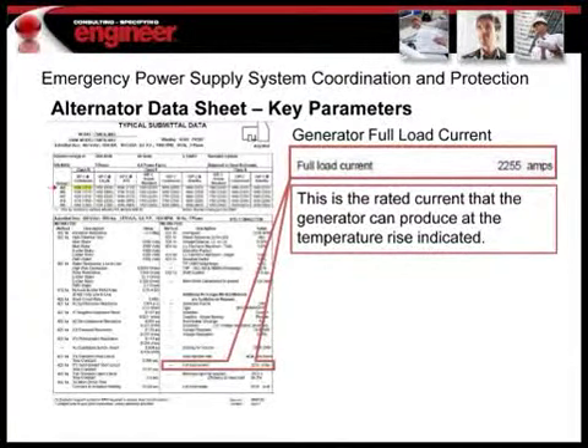The full load current of the generator is the next big item. Now, obviously, here we're looking at a 1,500 kW generator. So this is the rated current that the unit can produce, and it's always tied to the temperature rise that we're talking about. In this case, we're talking about an 80-degree rise with 2255 amps for that generator.